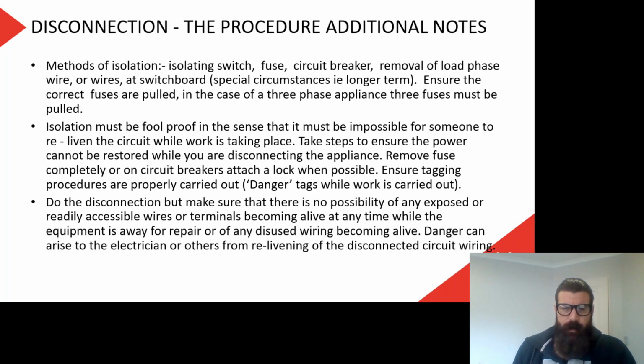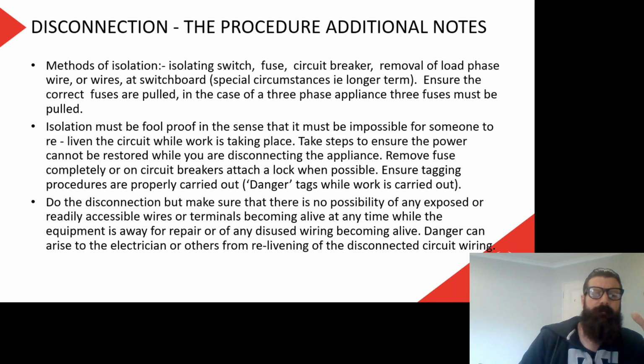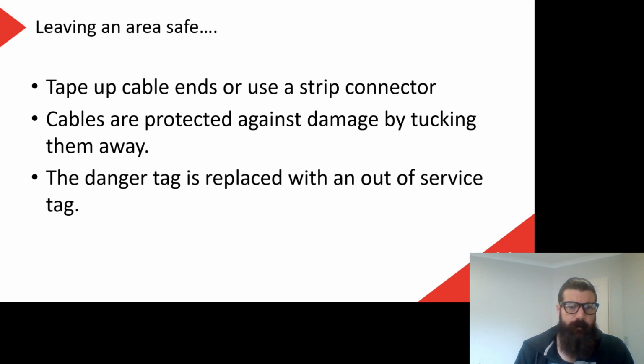So we need to make sure there's no possibility of any exposed or readily accessible wires or terminals becoming alive at any time while the equipment is away for repair, or if any disused wiring becomes alive. Danger can arise to the electrician or others from relivening of the disconnected circuit wiring. So if we're taking away an appliance to get repaired, or we're removing something that needs to be taken away, then we need to make sure that we're not leaving the ends of the wires remaining exposed, because somebody else could come along and reliven that, or we might reliven it before we go, so that everything else on that circuit's operating again. So we need to make sure that we make safe those circuits, and make sure that nobody else can come in contact with the wires.